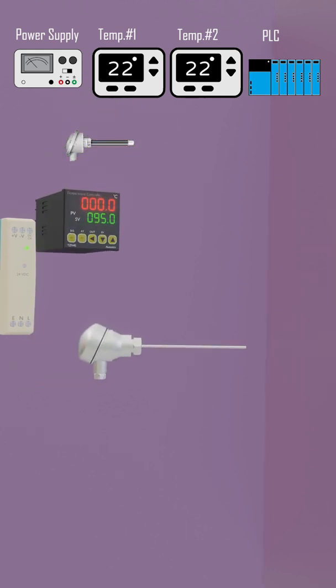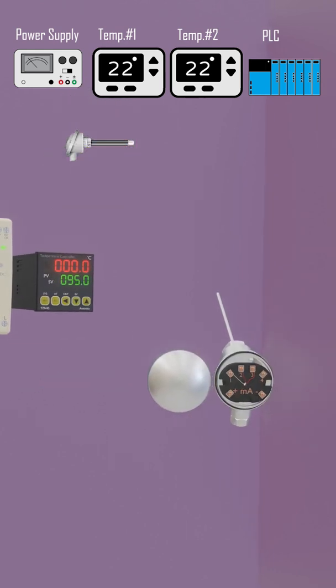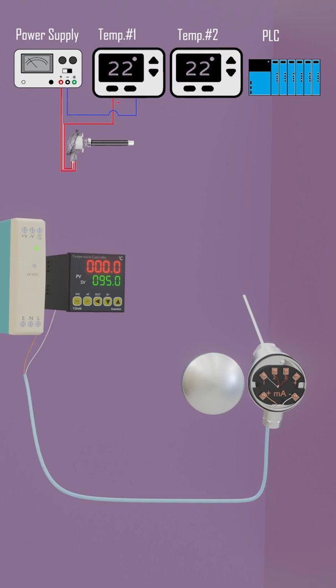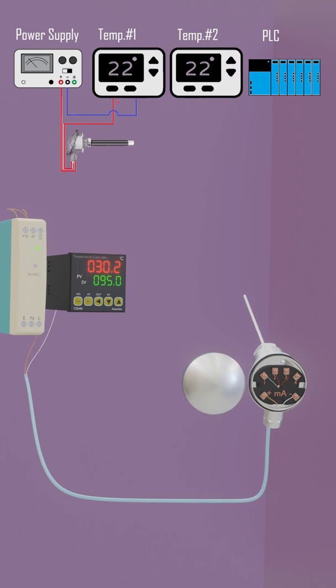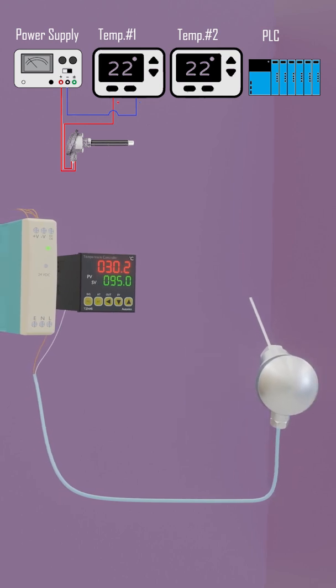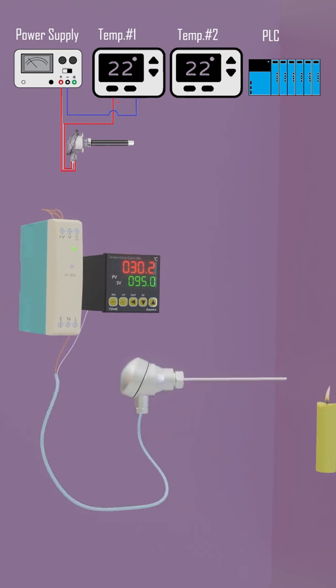We need a temperature controller and a temperature transmitter to sense the temperature. We will connect power supply wires and analog signal wires from temperature transmitter to the analog input of temperature controller to make a series loop.